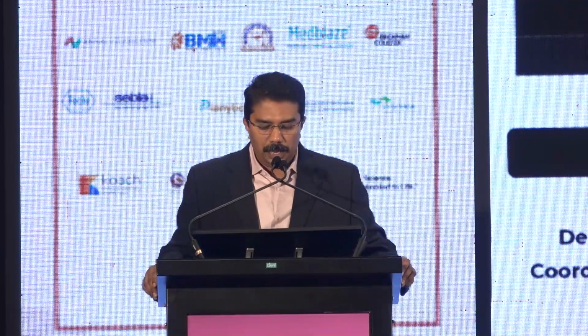But the critical alarms did not work as they were switched off by the allotted nurse the previous day. So the investigators concluded that alarm fatigue experienced by nurses working among constantly beeping monitors contributed to the death of the patient. And this served as an eye-opener for agencies to focus on alarm fatigue as a safety issue. In 2013, the JCI Sentinel Event Report alerted about medical device alarm safety in hospitals. And between 2009 and 2012, there were 98 alarm-related events, of which 80 resulted in death of the patient and 13 resulted in permanent loss of function.